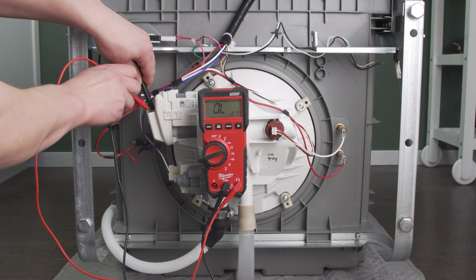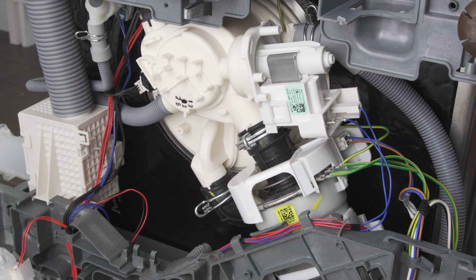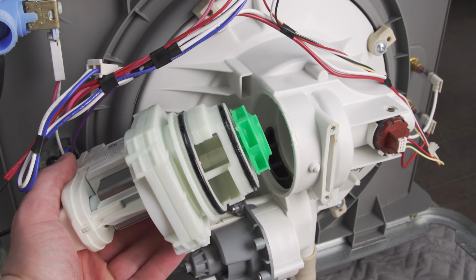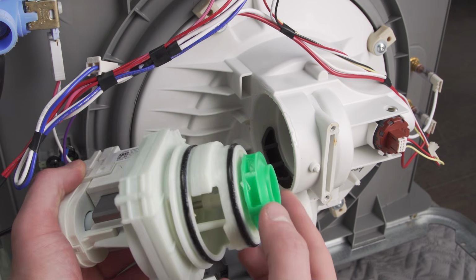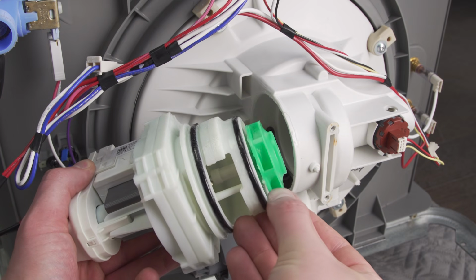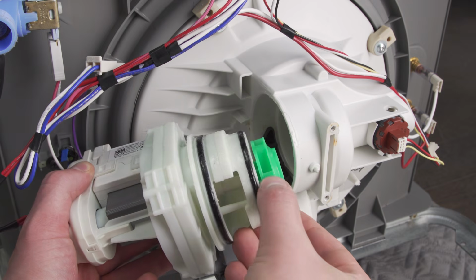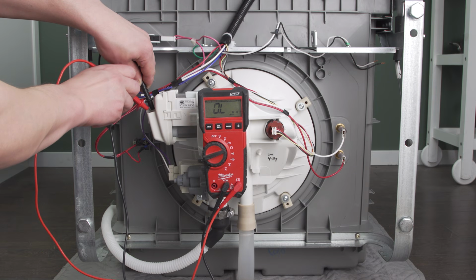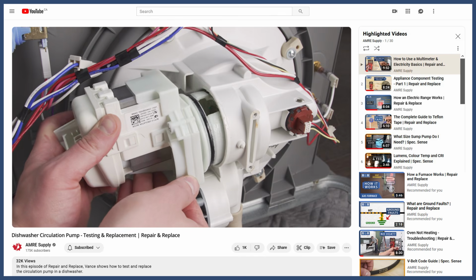If there is no continuity, an infinite reading, or a resistance in the millions of ohms, then the pump has failed and should be replaced. Some circulation pumps have additional terminals for a built-in heater. These will have a resistance reading of 10 to 30 ohms. A continuity test will only show if the pump has failed electrically. It's still best to check to see if there's anything jammed or blocking the impeller. If the pump has failed the continuity test or does not spin freely, then it's best to install a new one. You can see how to replace the pump in the video linked below.